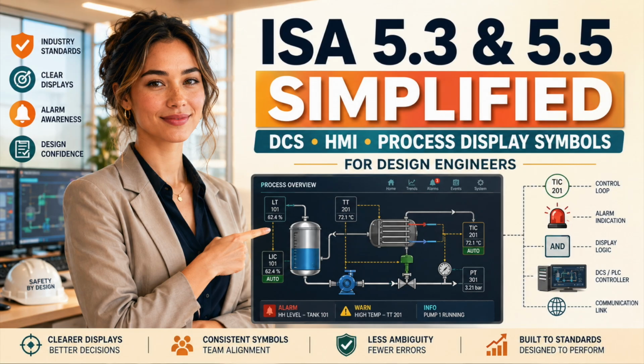The lead engineer must therefore treat the human-machine interface philosophy as a project design deliverable. The project needs approved rules for symbols, process flow orientation, color semantics, display hierarchy, alarm presentation, data quality, command and feedback, backup control, package integration, navigation, and change management. The process engineer must verify that simplification preserves the correct operating story.